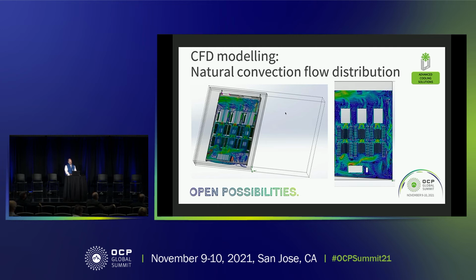It looks like a bit of a mess of lines, but what that's showing you is the trajectories that the flow takes. And what we look at very carefully is to make sure that there's no recirculation of the fluid from the hot layers at the top down to the cool layers at the bottom, to make sure that we have a good stratified temperature distribution going through.